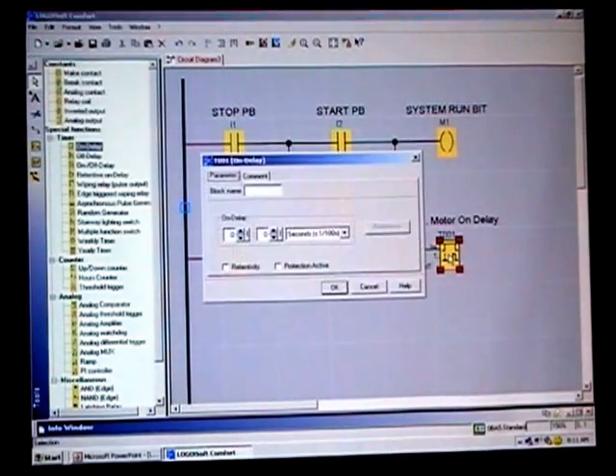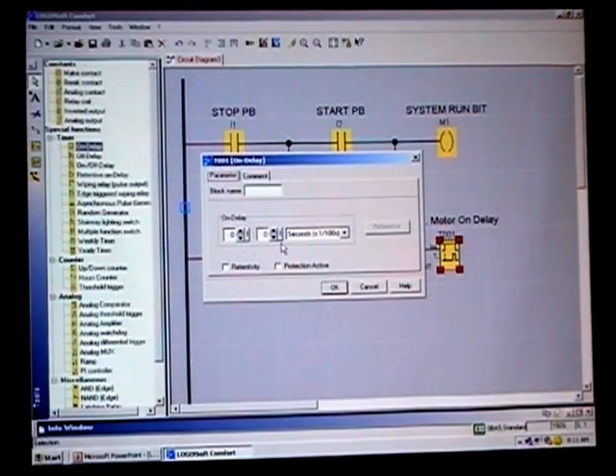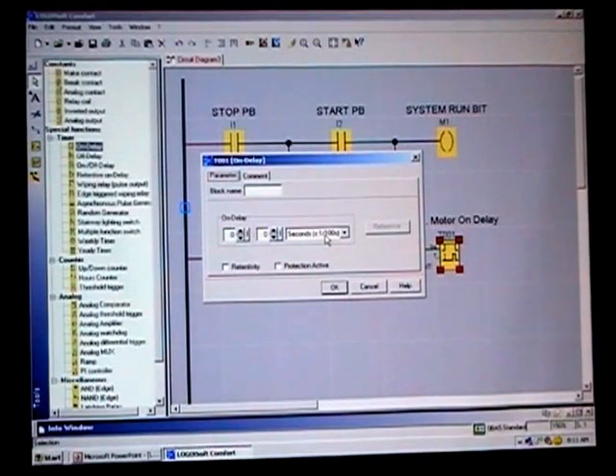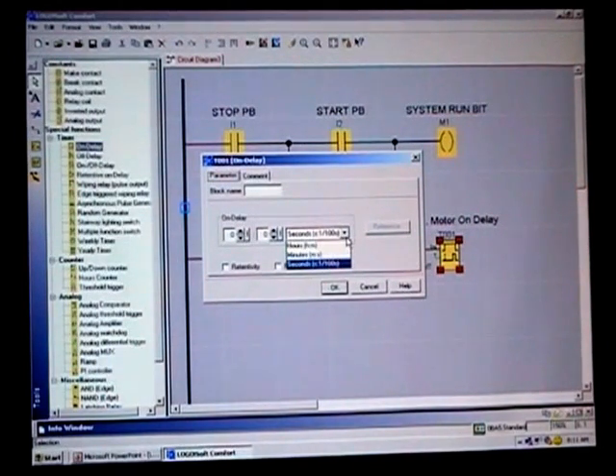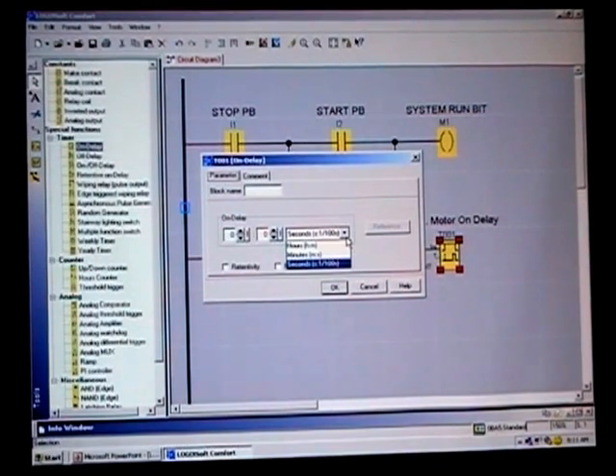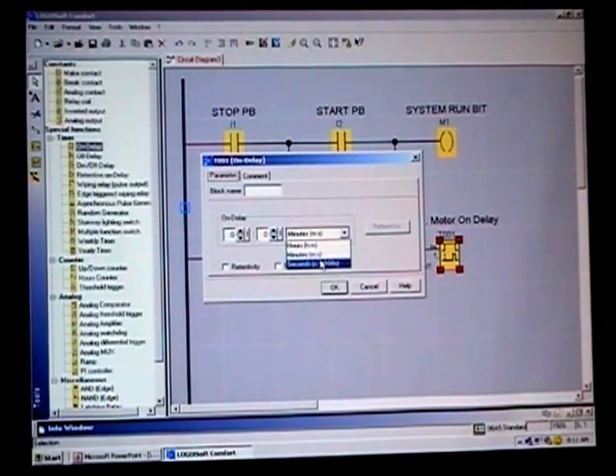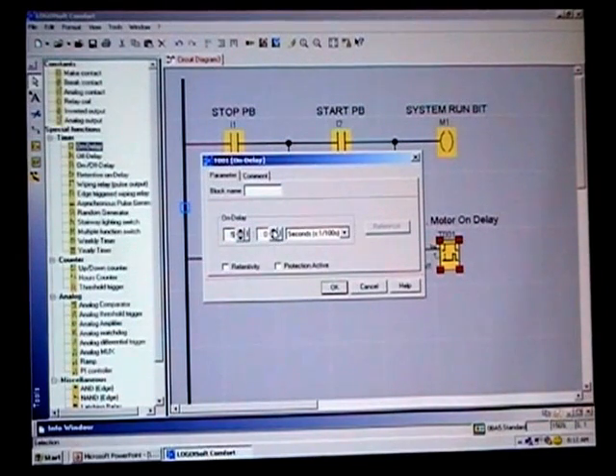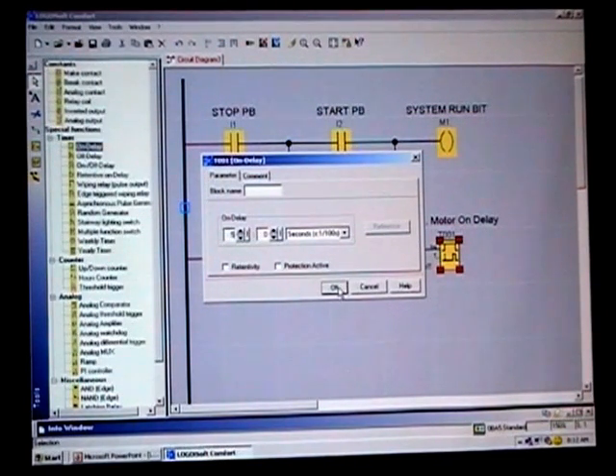Double-click the timer to set the on-delay. Notice I have full seconds and one-hundredths of seconds. I could set a 20-minute timer if needed. In this case we want a five-second timer, so set it to 5 seconds. If you set the right field to 5 instead, that would be five hundredths of a second — too quick to see. Block name, retentivity, and protection settings we'll cover later.